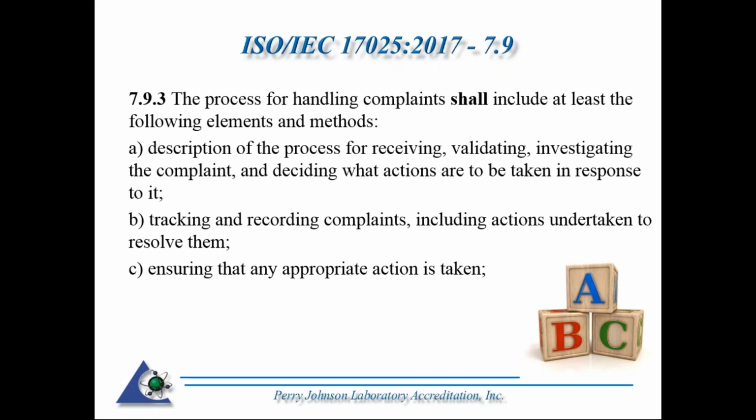So let's say a customer calls, looking at a report, and says, hey, you didn't take uncertainty into account in making a statement of compliance. Well, that's a requirement. You have to do that. If your investigation clearly indicated that the lab committed a nonconformance against a requirement, then it would be a nonconformance.